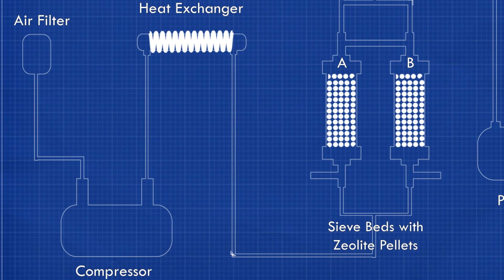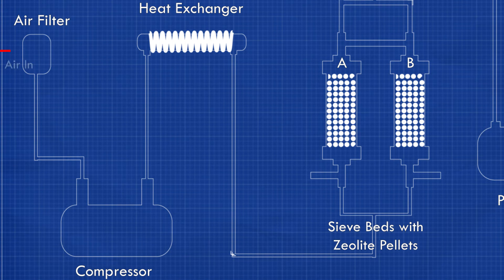First, the air filter filters out large impurities such as dust and pollen. This filtered air is passed to the compressor. The compressor compresses those gases to high pressures. This compressed air is then sent to the heat exchanger to cool down the hot compressed air. This air reaches one of two zeolite sieve beds.